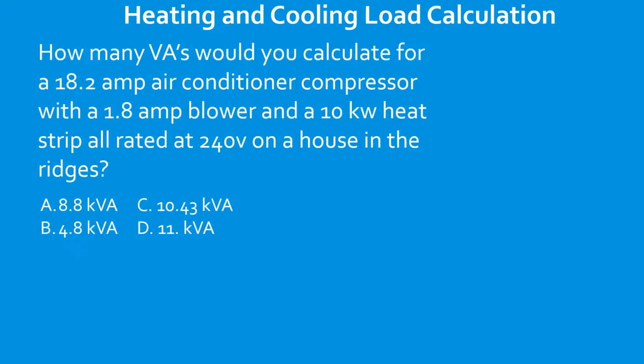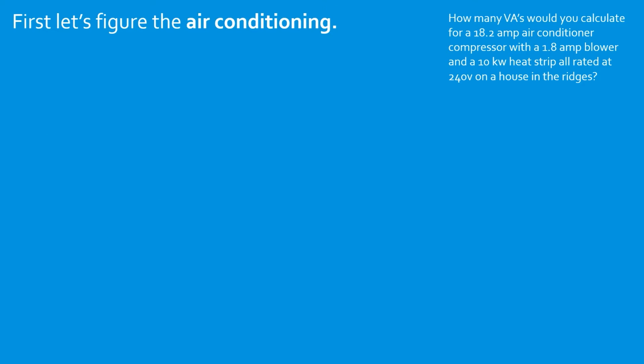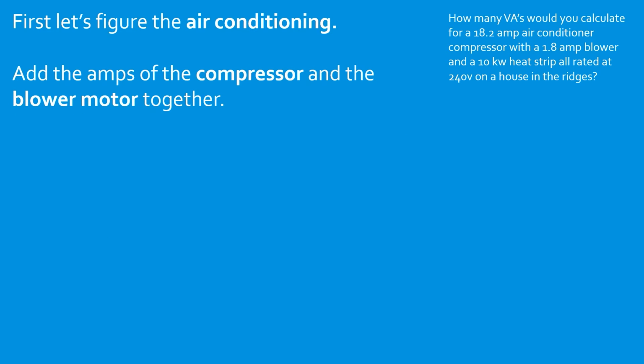Let's check it out. How many VAs would you calculate for an 18.2 amp air conditioner compressor with a 1.8 amp blower and a 10 kW heat strip, all rated at 240 volts on a house in the Ridges? Remember, we're going to use the larger of the two. So let's figure the air conditioning first. We're going to add the amps of the compressor and the blower motor together, and that will let us know the total that it takes to run the AC. We have 18.2 plus 1.8. That's going to give us 20 amps.